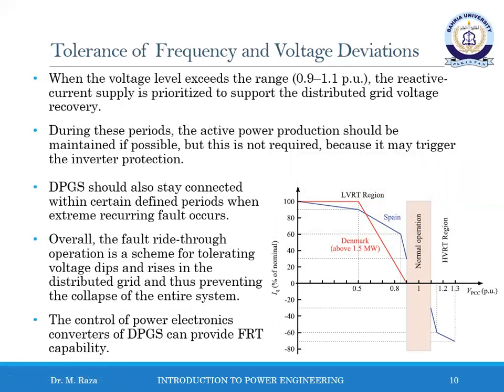As previously mentioned, reactive current from the distribution power generation system is required in the case of distributed grid fault. Here, the grid code requirement of injecting reactive current by the distribution power generation system is illustrated. It says that when the voltage level exceeds the range of 0.9 to 1.1 per unit, the reactive current supply is prioritized to support the grid voltage recovery. During this period, the active power production should be maintained if possible, but this is not required because it may trigger the inverter protection.